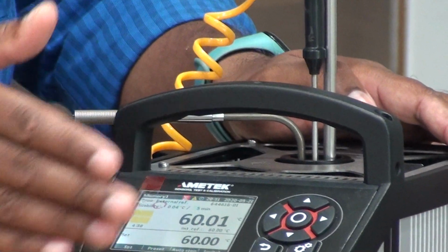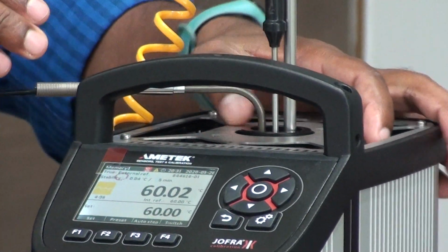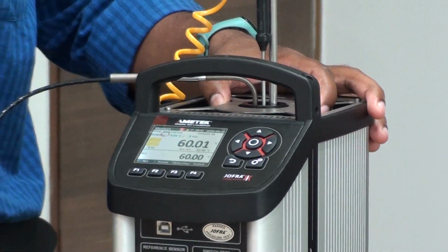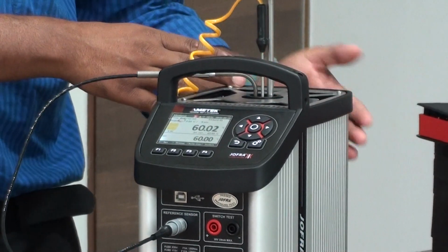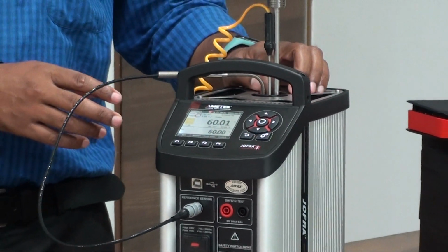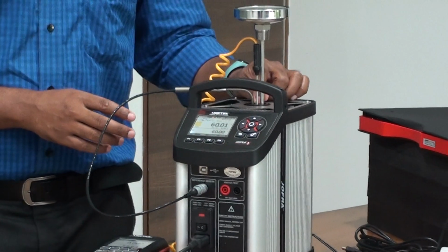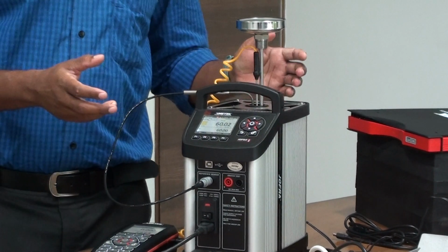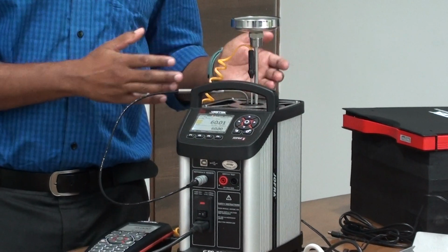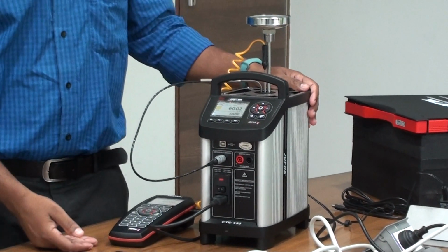and it is more accurate because generally people use an external reference sensor for calibration rather than the internal sensor, because the external reference sensor goes exactly where the calibration is happening. So most of the calibration agencies recommend using external reference sensors.